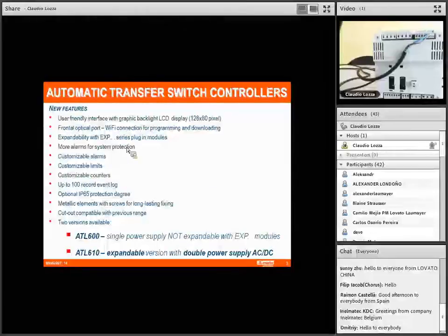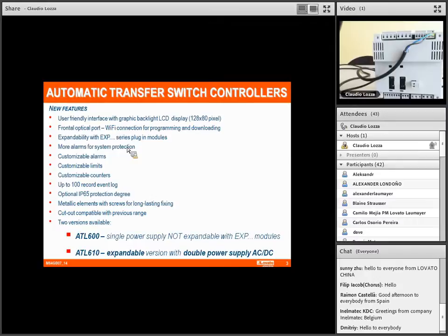Okay. Then with this device we increase the number of alarms. For example, now we introduce the alarm for the breaker protection trip for line 1 and line 2. We introduce the alarm for the generator if it's not available. And then some functions regarding maintenance. So we have 2 counters for each line that count how many hours line 1 or line 2 works, and how many operations the breaker for line 1 or line 2 performs. So this is very important for the maintenance of the system.